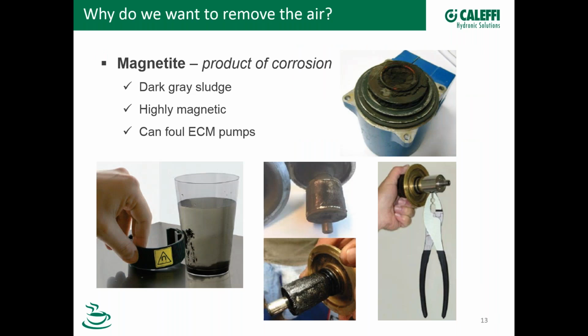Another product of corrosion is magnetite. Now, magnetite, here are some nice pictures showing that. It's a dark gray sludge, can cause a lot of damage. It's highly magnetic, as you can see here, and it can be a real problem for ECM pumps.